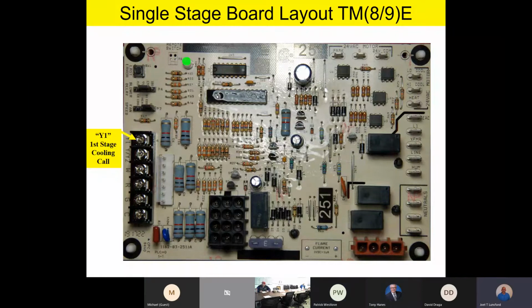All right, so here we go, team. Looking at the left-hand side of the board, we're going to start with our low voltage terminal strip. Y1 will be our first stage cooling call. Again, this board is single stage heating, but up to 2-stage cooling capable. Y/Y2 will be our second stage cooling call.